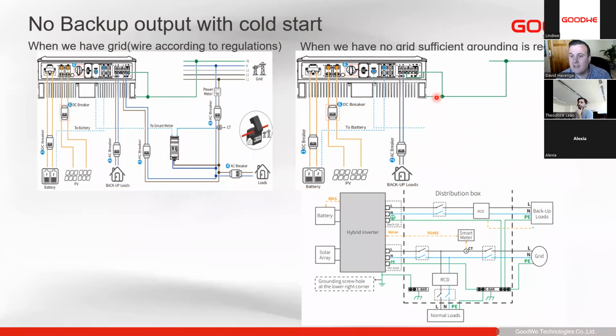This is a safety regulation in most countries, but the inverter does require this to check that everything is correct. If there is no grounding on the site, your device may not start up, it will just remain in a waiting mode. This is a very small use case, but it is something we have encountered, especially on the EM and ES devices, where customers install them without utility, and the devices do not start because there's no ground connected. So we need to make sure that there is always a good grounding connection.